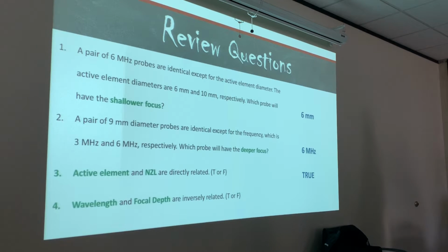Near zone length is the distance from the transducer to the focus. Right now we're talking about focal depth. Focal depth is another term for near zone length. All I'm doing is putting the synonyms in there, so you guys know the difference. Near zone length also goes by focal depth, focal length, and near zone.